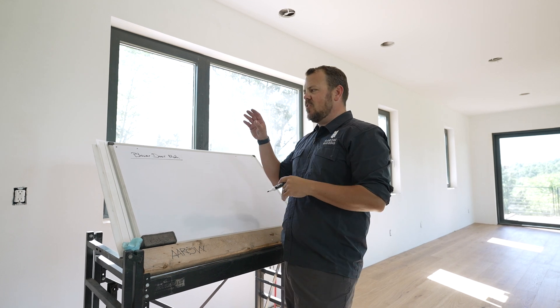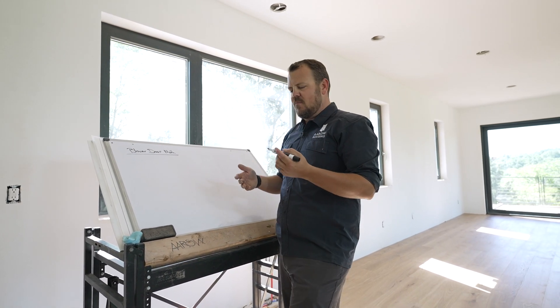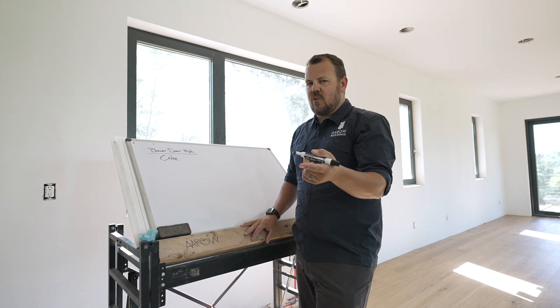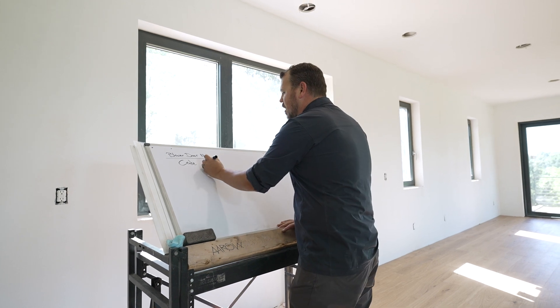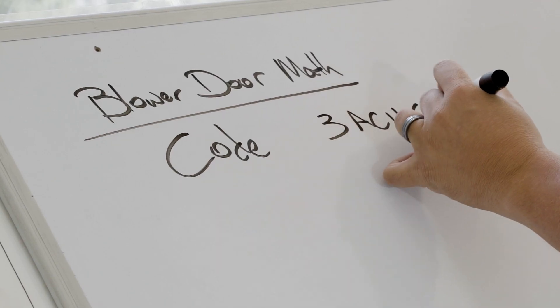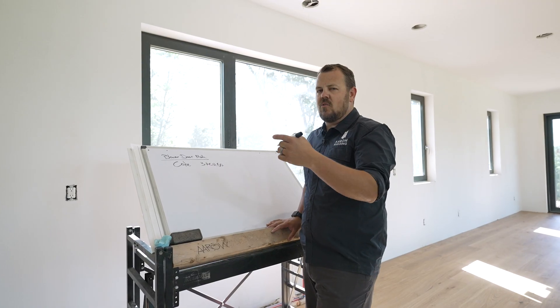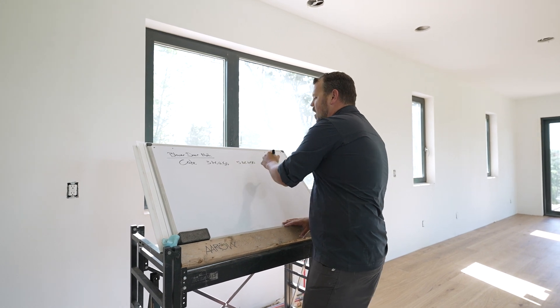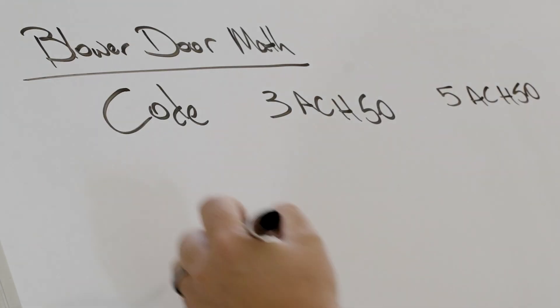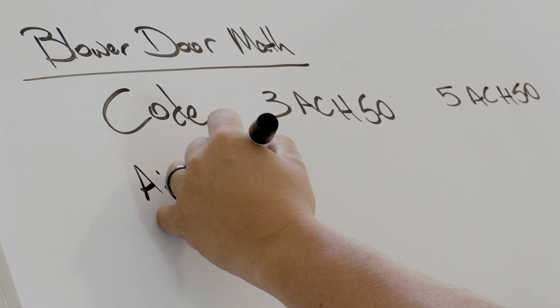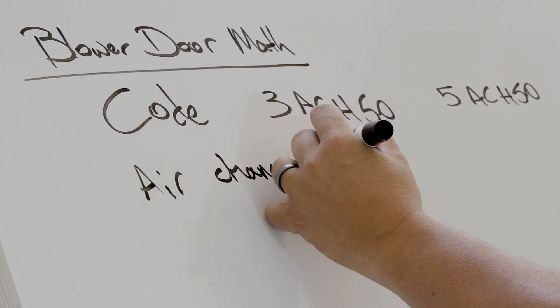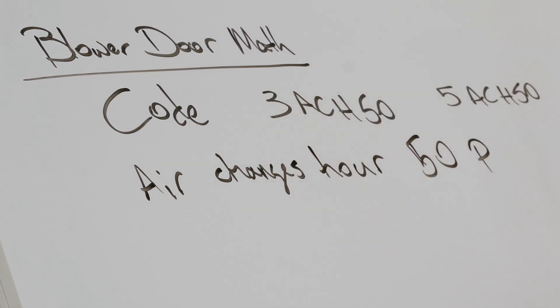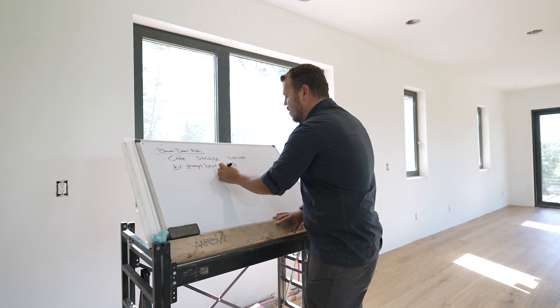We have to start the blower door conversation with what code says. The 2021 code changed — in my market it's 3 ACH50, and the new code for the whole nation is 5 ACH50. That means air changes per hour at 50 pascals of pressure.